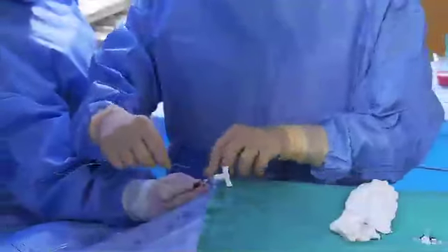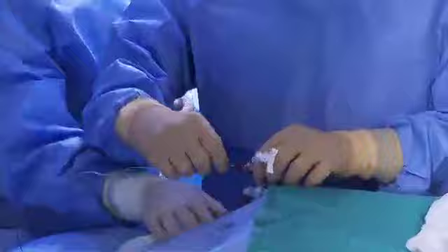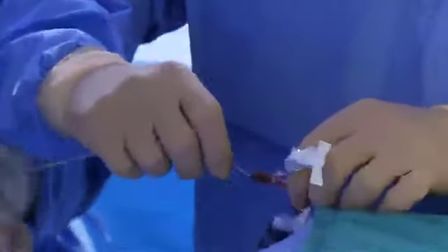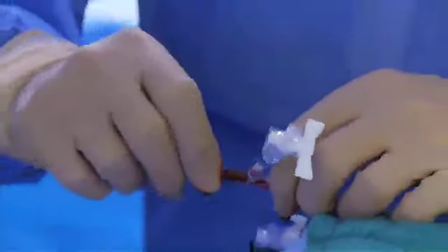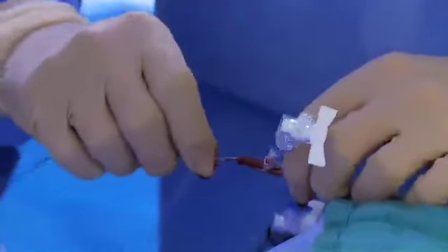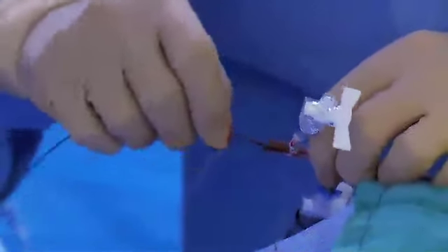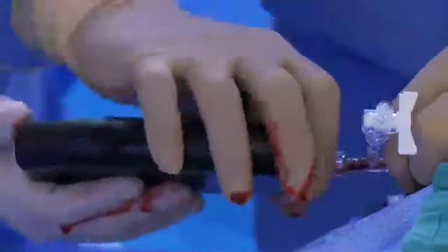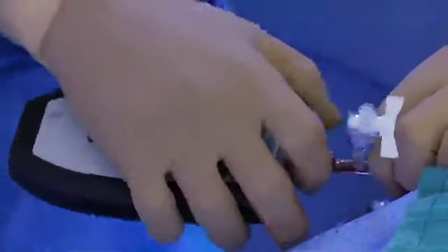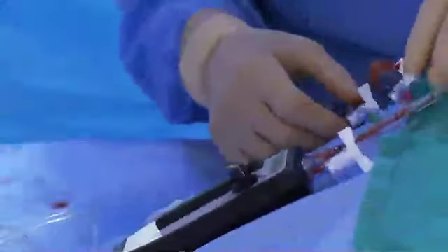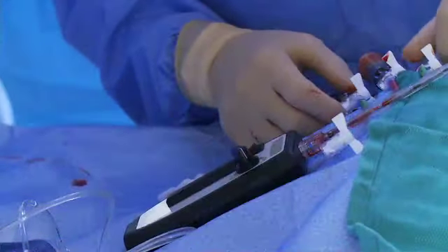Flush the aspiration lumen with at least 2 cc of heparinized saline and close the stopcock. Under fluoroscopy, insert the dispersion wire of the ODU into the catheter guide wire lumen. Fully advance it through the catheter and attach the ODU to the catheter by tightening the rotating luer. If there is difficulty advancing the dispersion wire, inspect the catheter and/or wire for damage.